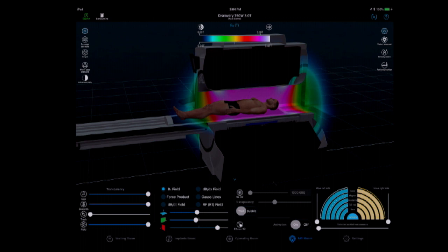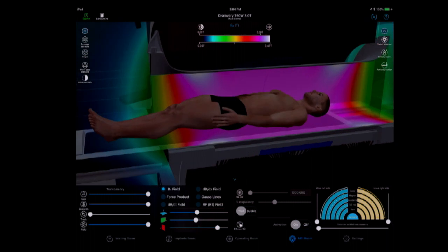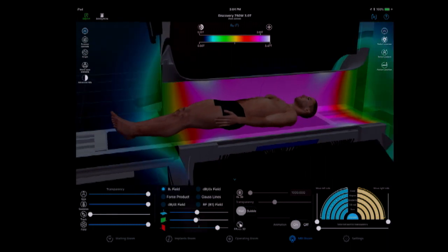When they label it to be 3 Tesla, what they really mean is up to a 3 Tesla scanner, not field. Because they recognize that one of the first things to learn is that the fields are not necessarily what you think they are. Secondly, the static field is not greatest in the center. It's actually greatest out there towards the periphery for all of these systems. I'll show you. And it is different for every system.